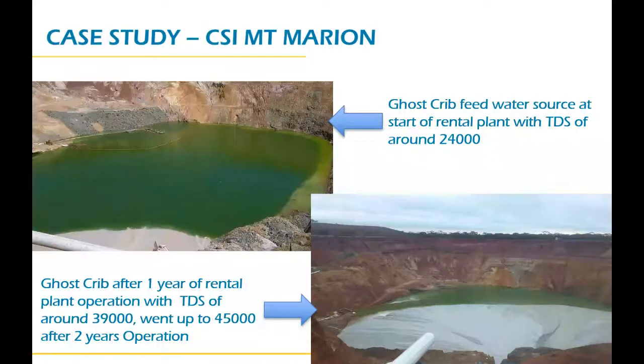Initially, this project was delivered for 6 months rental only. When we started the rental plant, as you can see in the top picture, the ghost crib where we were taking feed water from was full of algae, with TDS around 24,000. Rental was extended beyond the initial 6 months and into the first year. In the bottom picture, the white grayish area is pretty much empty, with only a little water left at about 39,000 TDS. The plant continued to operate for around 2.5 years, and by the time we finished, we were operating on about 45,000 TDS of water. It was quite challenging, and our process team was always working with the client to improve plant performance and give continuity of water supply.